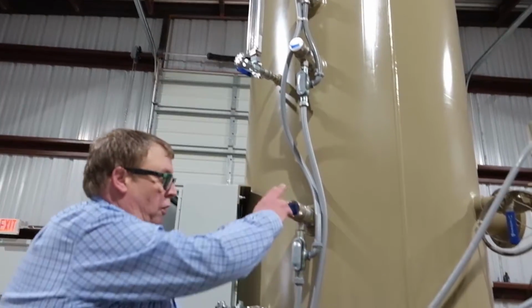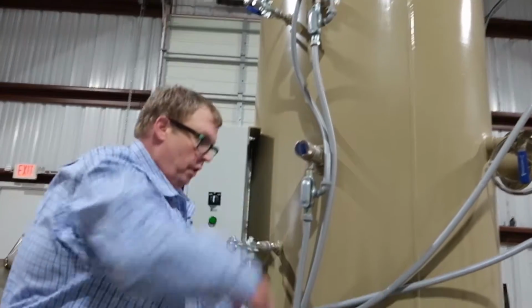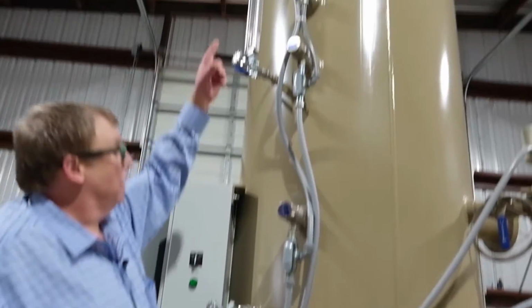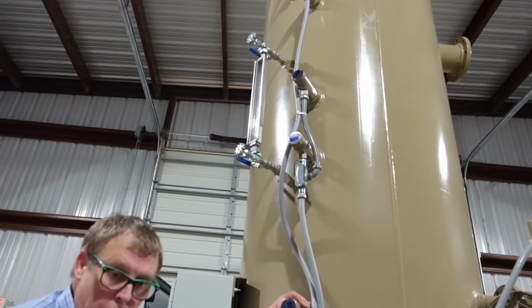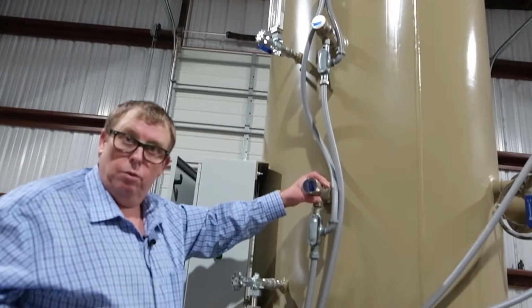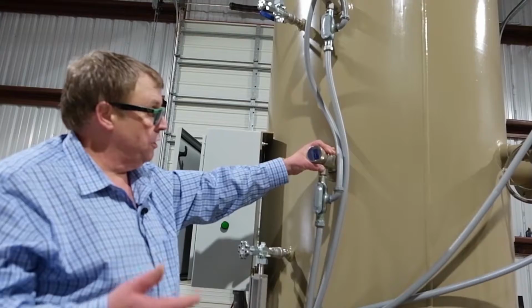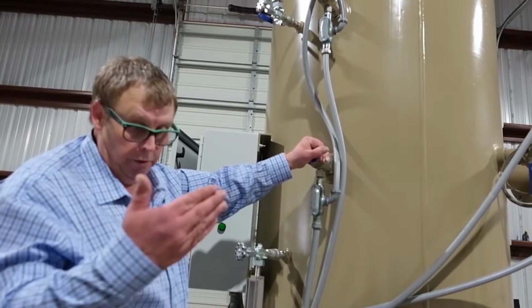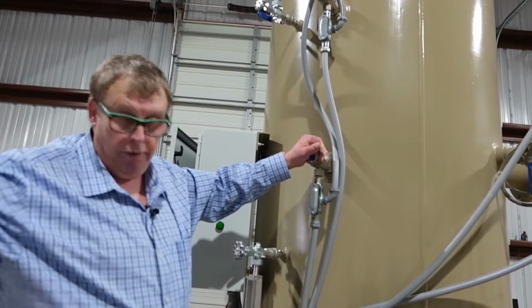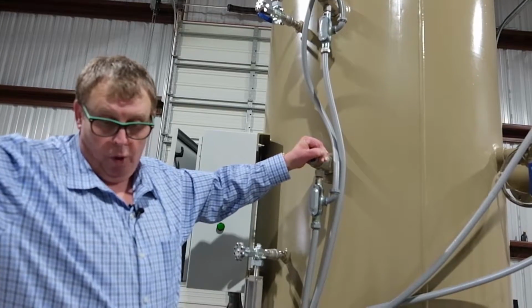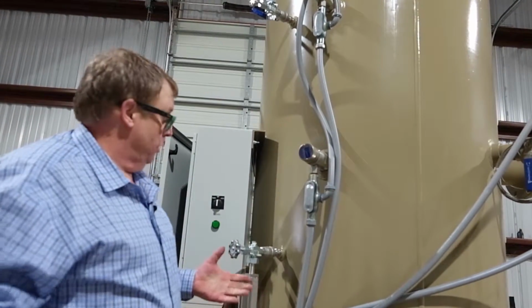Now you'll notice we have a 3rd level switch here. This 3rd level switch on both your lower side and your higher side is an emergency level switch that would allow you to tie in from your automation, and it'll turn the flare off. It'll also turn off at your wellhead if you so choose to use that.